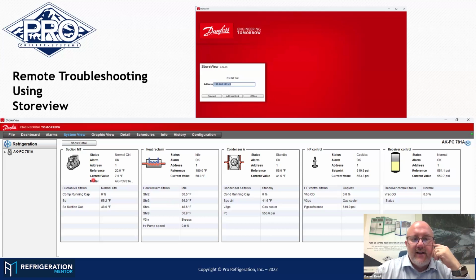And so you can see here, I'm looking at my suction. What's my suction status? In this particular moment on this system, it's normal control, meaning there's no alarms. It's okay. I've got a 20-degree suction set point, and it's currently seeing 7.6 degrees. So right away, before I even go any further, I expect that if my reference point is 20 and I'm at 7.6, I better not be running any compressors. There's no reason for that, right? So I'm in a normal control status. My compressor running capacity is 0%. Perfect. That's what I expect.